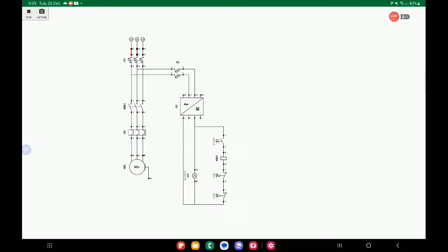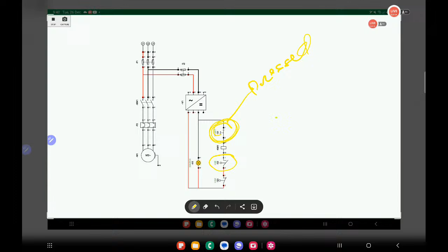So in this setup right now, if we run the system, run, run, I have source light, and if I press the start button, now the electrical motor started running. So if the boom of the lifeboat Davit, or whatever the activation point, reaches the limit switch, which is this LSB, it opens and stops our circuit. So even if the start button is pressed, because of this limit switch, this electrical motor stops also. That's how important the limit switch is to the electrical motor.